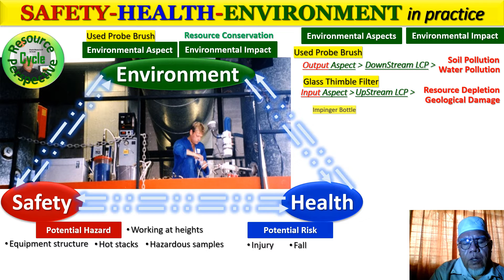This activity is now common in this country. Requirement for stack sampling is enormous, and apart from EIA approval terms and conditions, there are other kinds of written approval issued by the authority requiring premises with air impurity discharges through their stacks or chimneys to perform periodic stack sampling of several air impurity parameters such as dust, sulfur oxides, nitrogen oxides, and perhaps even heavy metals, and also acid mist, depending on where they belong in the Clean Air Regulations Third Schedule.